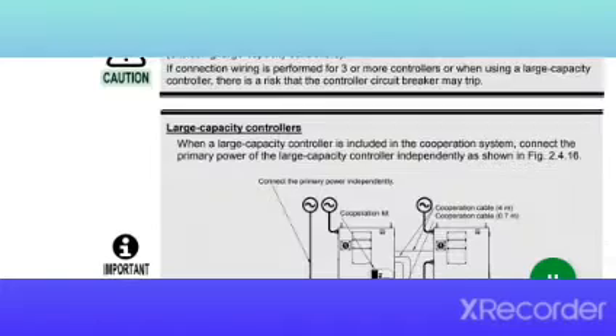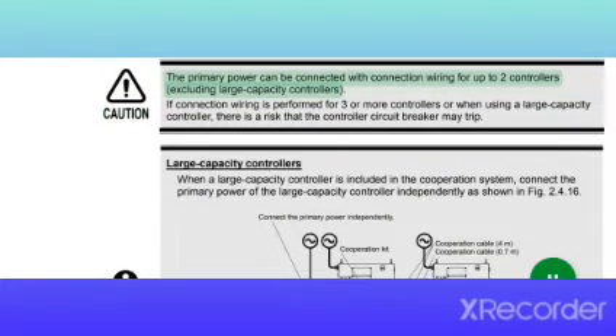2 to 22. Caution. The primary power can be connected with connection wiring for up to 2 controllers, excluding large capacity controllers. If connection wiring is performed for 3 or more controllers or when using a large capacity controller, there is a risk that the controller circuit breaker may trip.